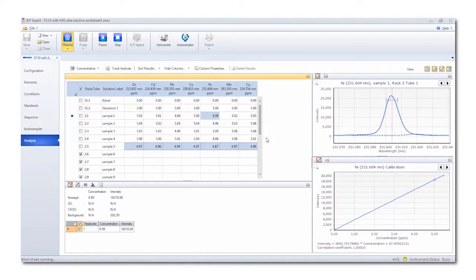The Agilent Advanced Valve System also uses a preemptive rinse. This is where the probe moves to the rinse station prior to the end of the loop fill. This enables rinsing of the probe and valve even before the switch to read the sample. The outcome is excellent washout of the AVS, with 4 orders of magnitude washout achieved, even with no additional rinse time entered into the method, and highest throughput possible.